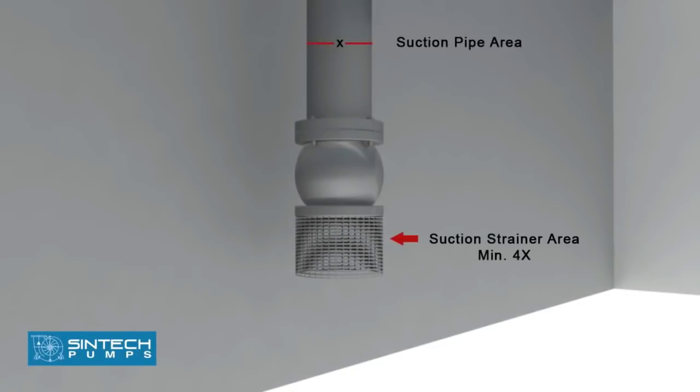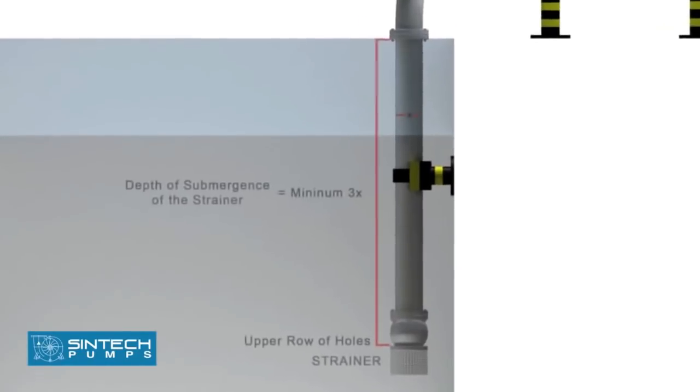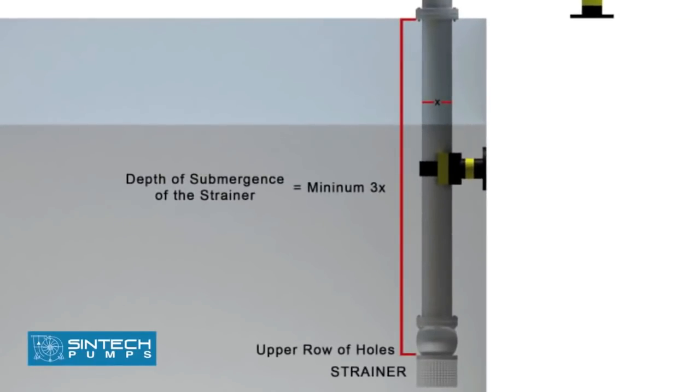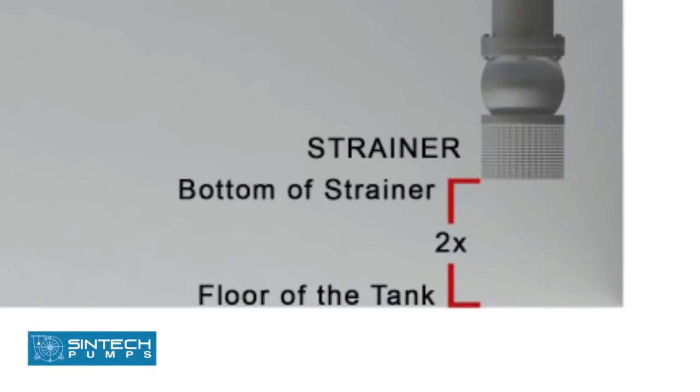The suction strainer must be at least four times the suction pipe area, and the mesh size should screen out solid particles that would clog the impeller. The minimum depth of submergence of the strainer should be at least three times the pipe diameter, measured from upper row of holes of strainer. The distance between the bottom of strainer and the floor of the tank should be considered as two times the pipe diameter.